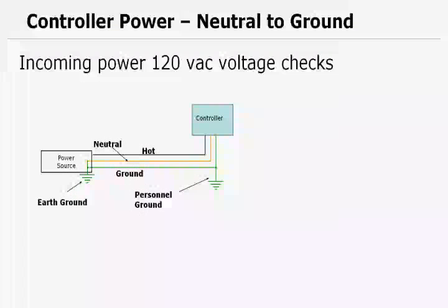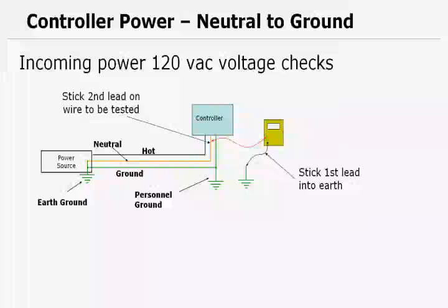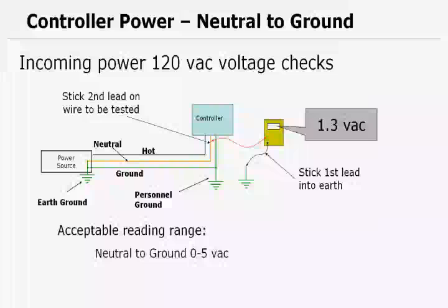Now let's check a reading from neutral to ground. Put our voltmeter first stick into the earth, second stick onto the neutral wire. And let's just use this as an example. We've got a 1.3 volt AC reading. Well, 0 to 5 volts is considered an acceptable reading. Anything above 5 volts is a problem.